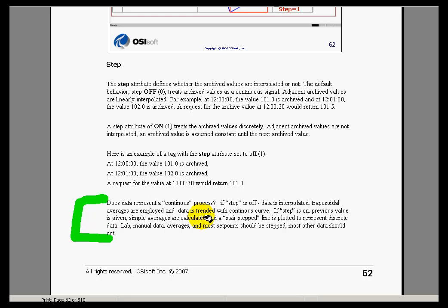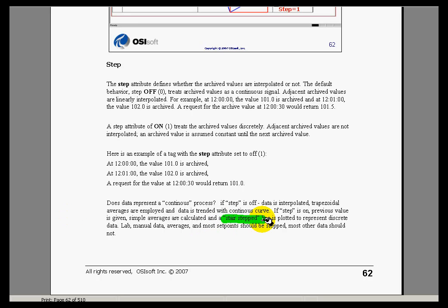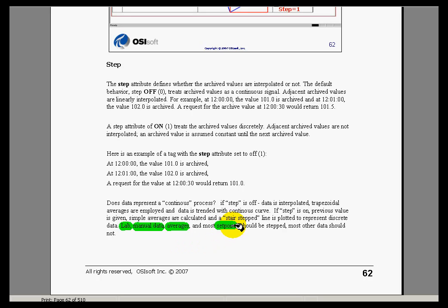For example, when you're doing things like averages, we do different types of calculations — simple averages versus interpolated averages. When we set Step equal to On versus Step equal to Off, there's of course the stair-step line on the plot. In general, what we suggest is any type of laboratory data, manual entered data of any type, any averages, and set points should be set with Step equal to On. Just about every other type of data should not have Step turned on.